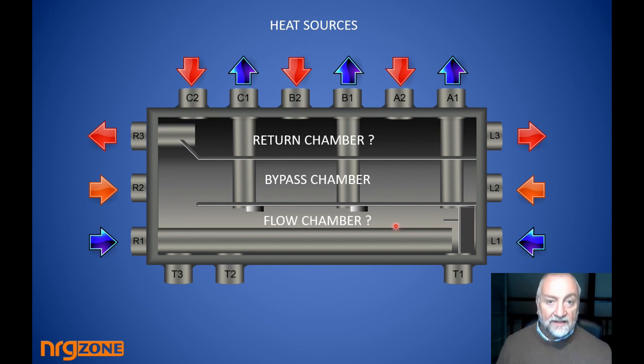So again, the naming of the zones is completely up to yourself, but we would still refer to it, just for our own usefulness, as the flow chamber being the one that is next to the vent sockets and whatever like that. But again, your discretion. The whole point of this talk is to tell you there's no absolute rules. The only rule that does matter is that when you put heat into a chamber, you take the heat from that chamber. When you take return water back to a chamber, that's where you return back to your appliance or appliances from.